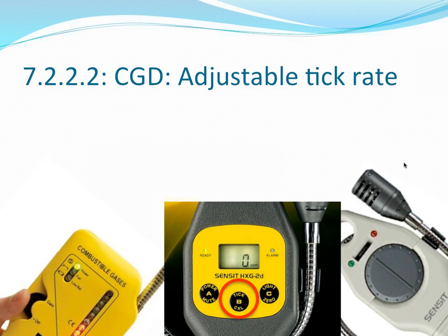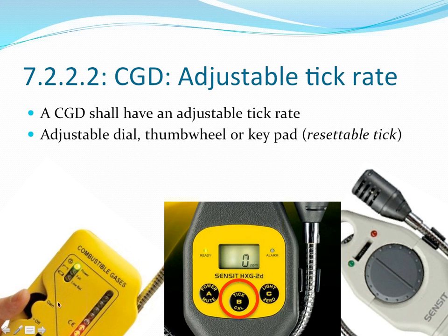So there's various brands and models of combustible gas detectors. One of the listing points on the standard is that it must have an adjustable tick rate, and that's achieved in different ways, through an adjustable dial or a thumb wheel, like in these two products here on the back right, Leakator 10. Leakator Junior has a high-low level switch. The Sensit TKX has a thumb wheel or dial on it. Or on the Sensit HXG2D, the tick rate can be controlled. That's the adjustable tick rate. So there's different means of control, or some kind of resettable tick rate has to be available in order to go from high to low and to do that kind of sniffing or ferreting out situation.